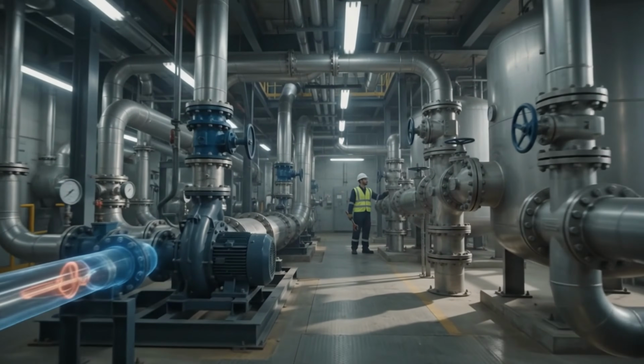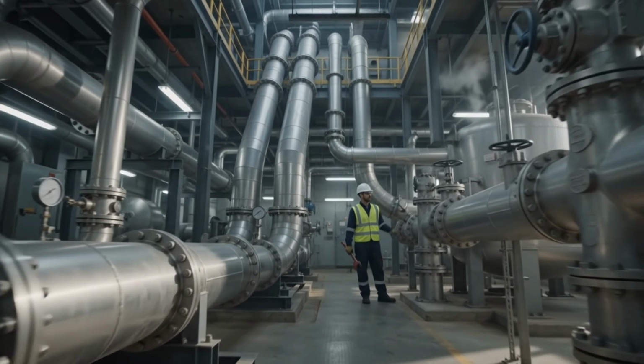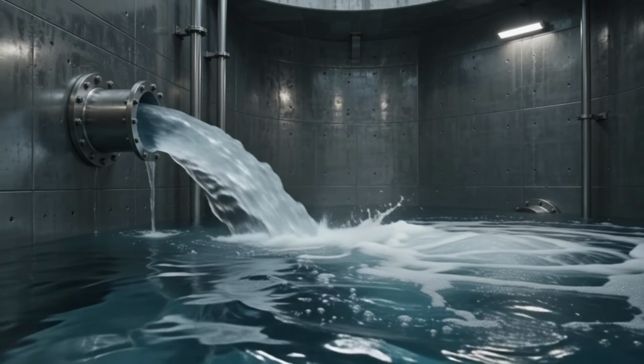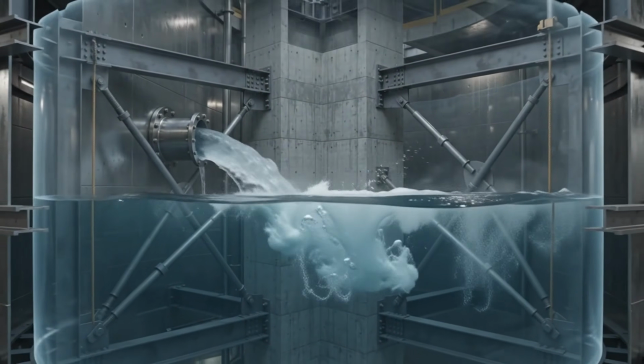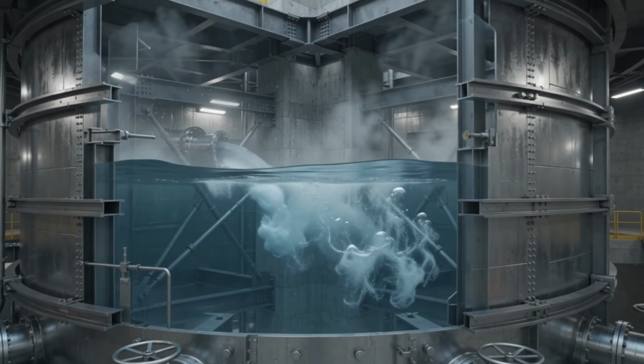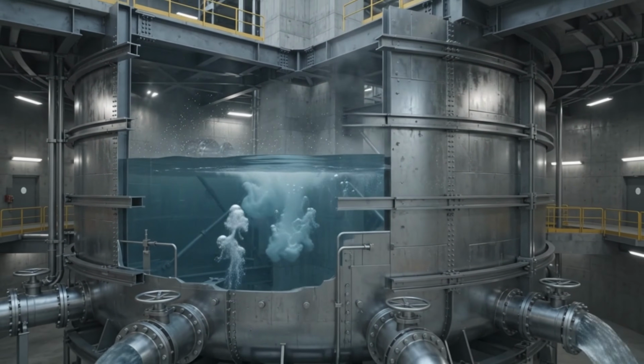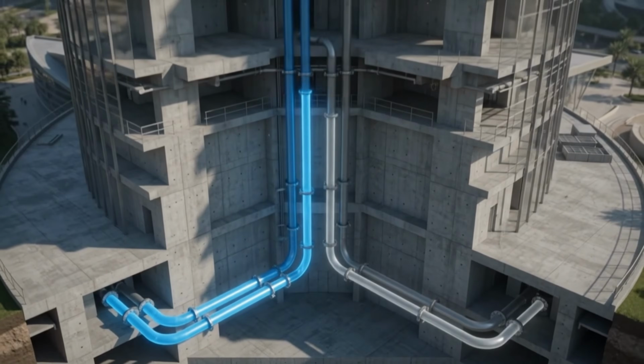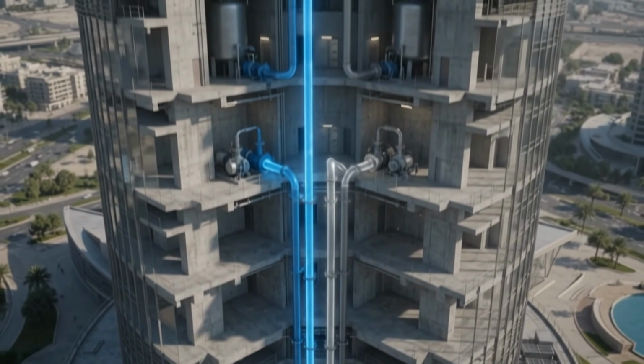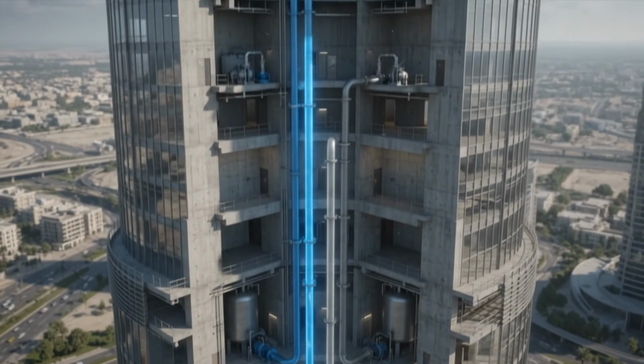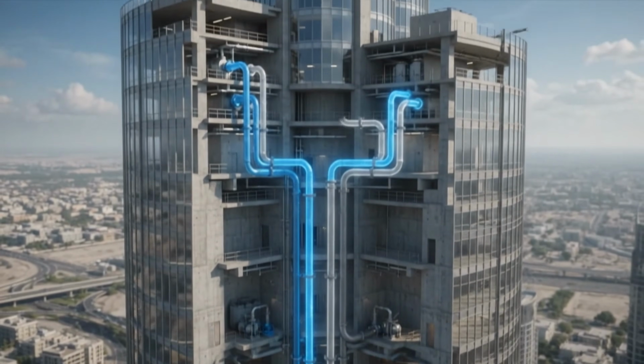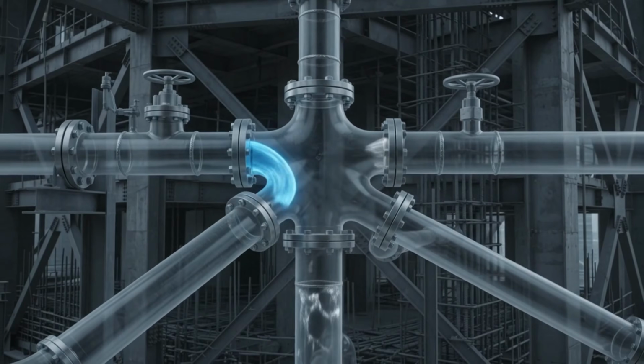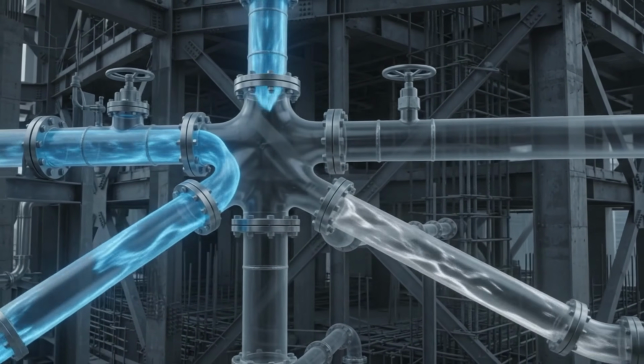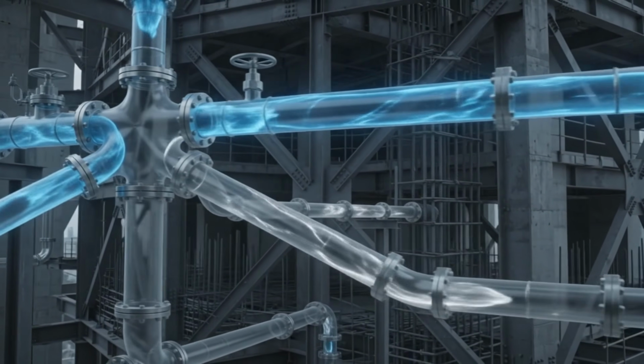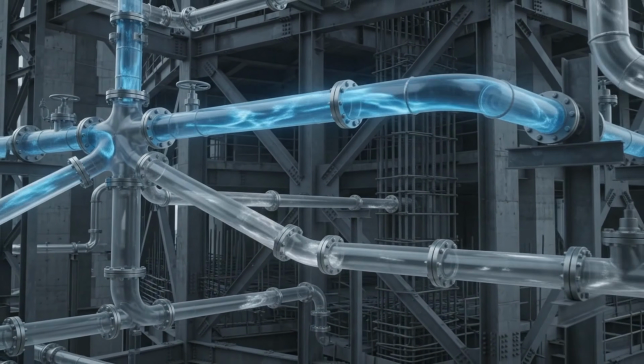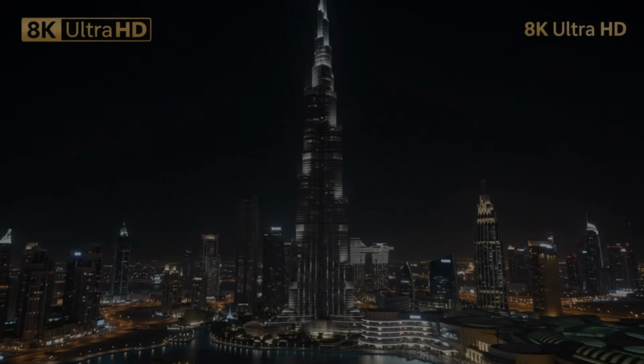Massive spaces hidden between levels, housing everything that makes this building function. Intermediate storage tanks at each mechanical floor act as relay reservoirs, absorbing the pressure from the pumps below, holding the water, then releasing it to the next stage. One carrying clean drinking water to every floor, the other carrying non-potable water for cooling, mechanical systems, and irrigation. This dual pipe separation is a critical safety and efficiency measure, ensuring drinking water is never contaminated by non-potable supply lines, no matter where they run.